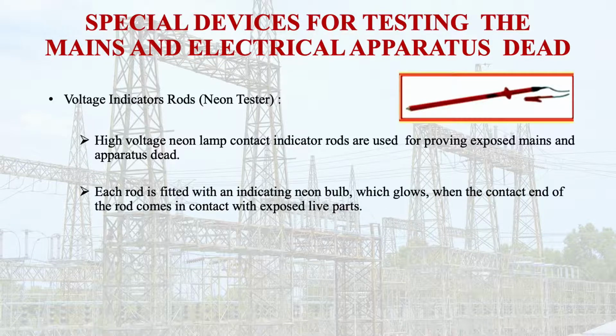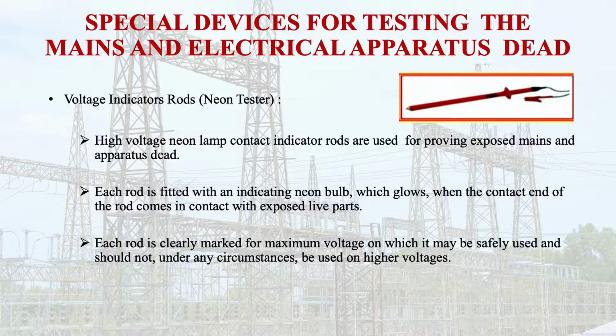Each rod is fitted with an indicating neon bulb, and it should always be tested before using. The bulb glows when the contact end of the rod comes in contact with the exposed live parts. Each rod is clearly marked for a maximum voltage on which it may be safely used, and should not under any circumstances be used on higher voltages. That means whatever maximum voltage is given there, it should be used under that limit only.